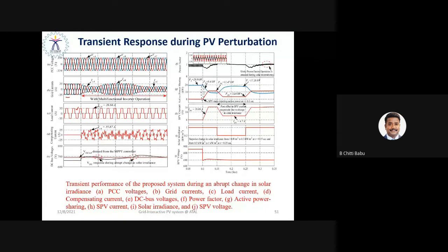As the control technique ensures sinusoidal current injection, and moreover it is in phase with the supply voltage or the grid voltage, the power factor becomes unity. And moreover, during a decrement in the load, the load component of the grid current is reduced from a particular value, the power reduced from 20.9 kilowatts to 9.4 kilowatts. In the meanwhile, the PV is supplying about 11.47 kilowatts.